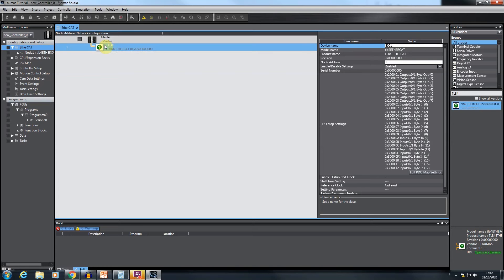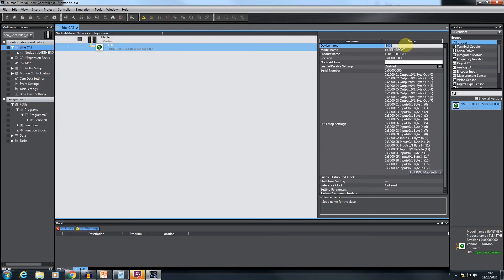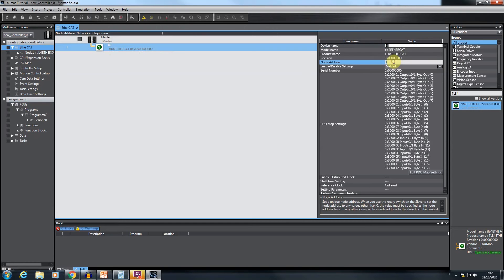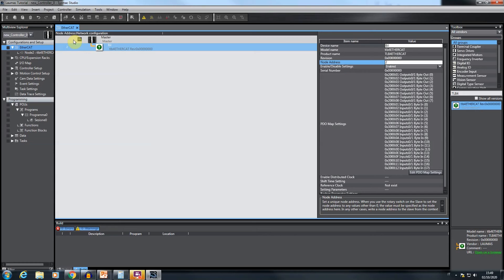Once available in the EtherCAT view, click on the TLB4 symbol to access a series of setup parameters by a tab open inside it. It is possible to set the name, used as instrument identifier in the PLC software, and the address, used by the PLC as instrument identifier in the physical EtherCAT network. In this project, the address is set to 2.